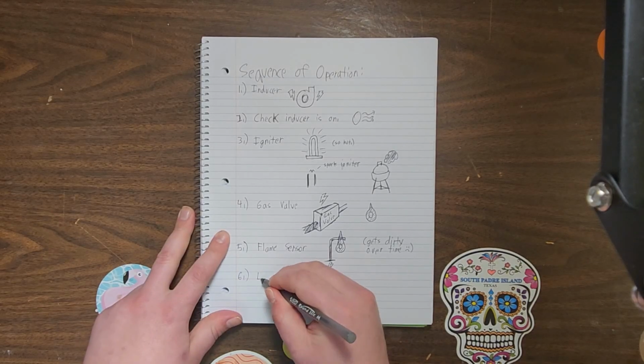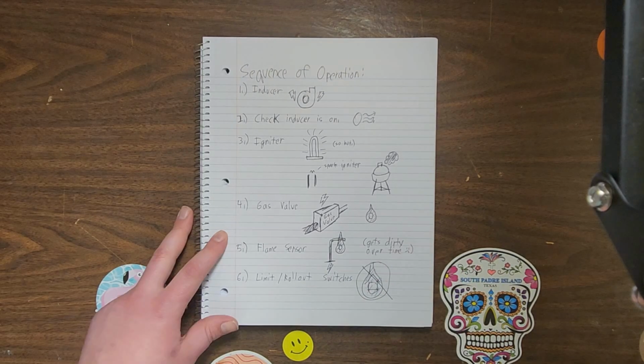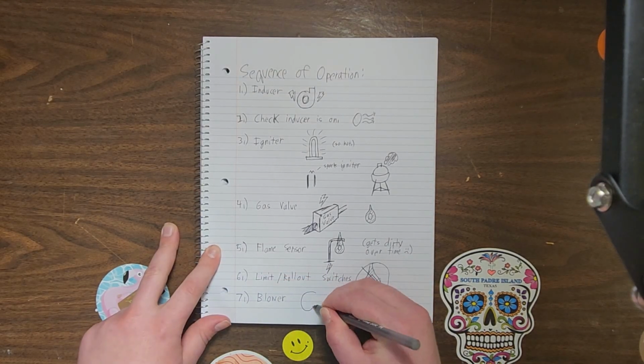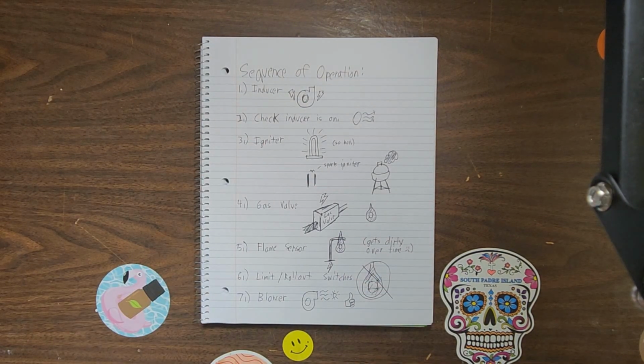Next are the limit and rollout switches. These make sure the flame is only in the heat exchanger and not in the furnace cabinet, so that way you don't set your house on fire. Finally, once all those have been passed, the blower will turn on, then distribute warm air throughout the home. So, we talked about a furnace. What is a heat pump?